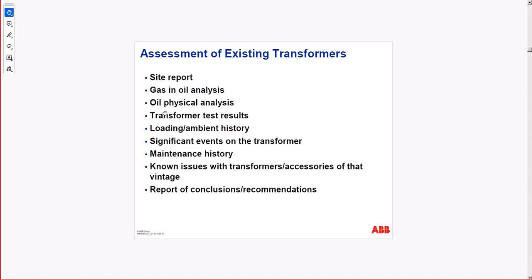Assessment: site report, oil physical analyzing, transformer test results, loading, ambient, significant event. You need to keep an eye on everything that happened on that transformer, like history. First of all, you need to have a benchmark from the manufacturer when they release the transformer. Then you need to have another benchmark when the installation of the new transformer happened. So all those parameters are the starting point, and from there on you're going to get the evolution of the transformer, and keep all those data, perform trending, and that will help with anticipation and prediction of the transformer failure.